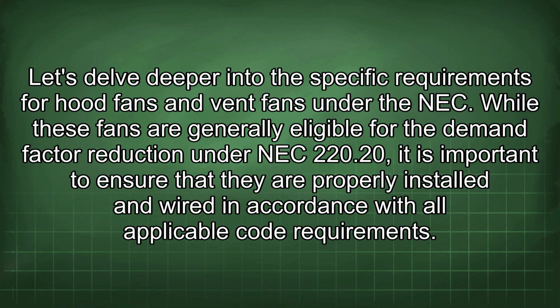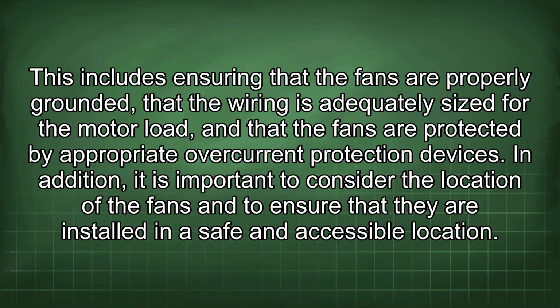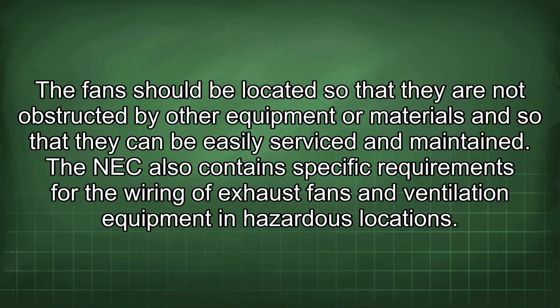Let's delve deeper into the specific requirements for hood fans and vent fans under the NEC. While these fans are generally eligible for the demand factor reduction under NEC 220.20, it is important to ensure that they are properly installed and wired in accordance with all applicable code requirements. This includes ensuring that the fans are properly grounded, that the wiring is adequately sized for the motor load, and that the fans are protected by appropriate overcurrent protection devices. In addition, it is important to consider the location of the fans and to ensure that they are installed in a safe and accessible location. The fans should be located so that they are not obstructed by other equipment or materials and so that they can be easily serviced and maintained.